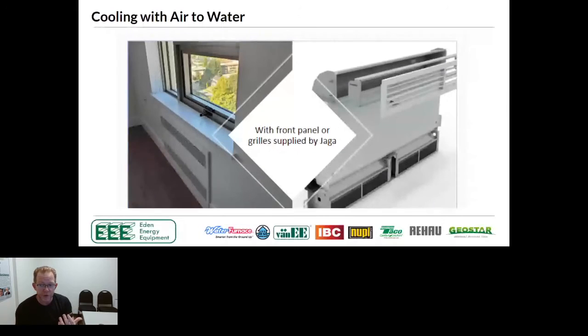If you don't want to see it, which certainly comes into play, there's other products on the market. So Myson makes a product called the iVector, I believe. It's designed to go underneath or recessed into the walls. This particular unit is what's called a Breeza 12. It's designed to be recessed into a wall. So I'm going to be using some of these upstairs. When I told you guys I'd run PEX up to do the bedrooms, I'm recessing these into the walls. I just have to get 1/2-inch PEX to them. They're my heating, my cooling, way easier than running new ductwork. I'm not ripping the walls all apart. It's very easy to get 1/2-inch PEX up into a room and deliver the BTUs I need for these.